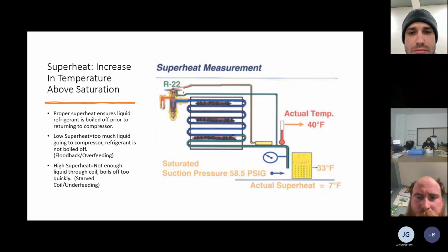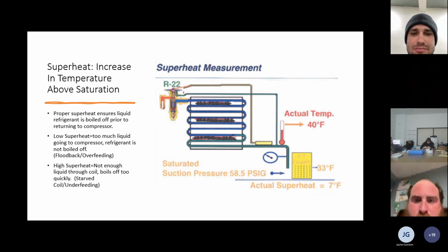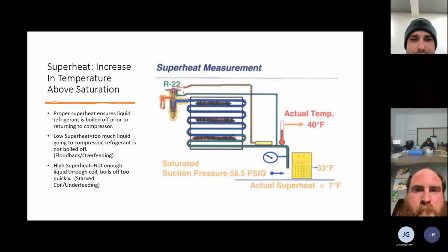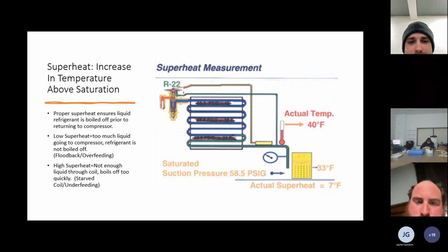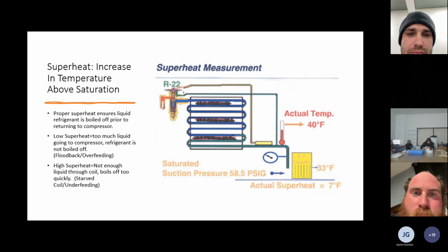One time it might go to 5 degrees, but the next cycle it might go to 3 degrees. That's a 2-degree superheat difference. If you go off your low swing each time, you have a basis to build upon. You're checking the same number every time, the valve in its open state, and you can adjust from there.